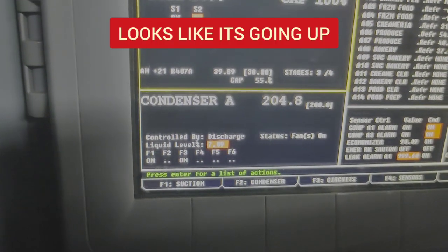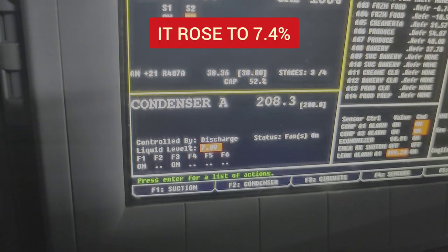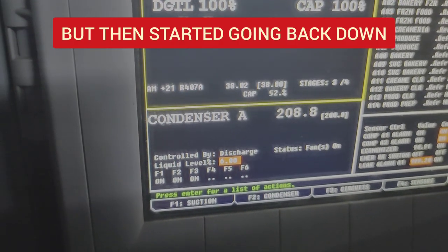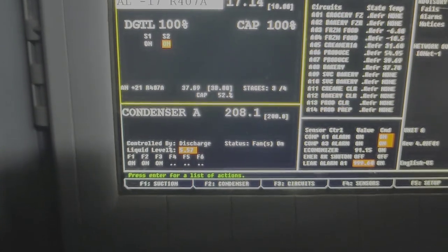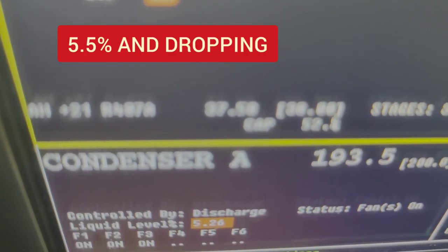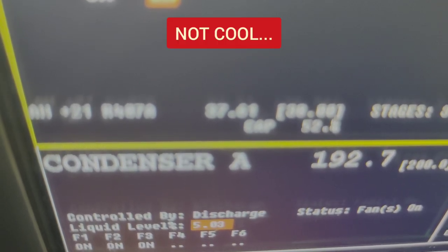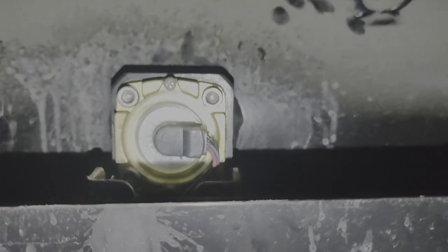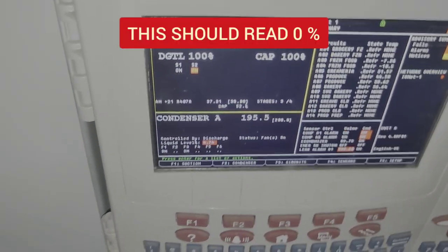There it goes. We got two side glasses on this rack. This one here was flashing earlier. At least now this one's cleared up, looks like. And then this one is still flashing. And I'll tell you what, this thing is pretty dry. I'm gonna go put another jug in it. It didn't even move that. I guess that's gonna be 0%.